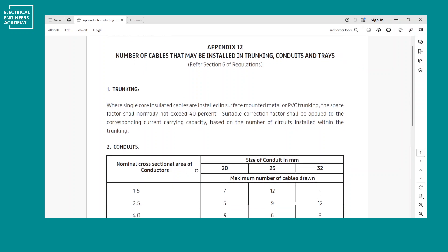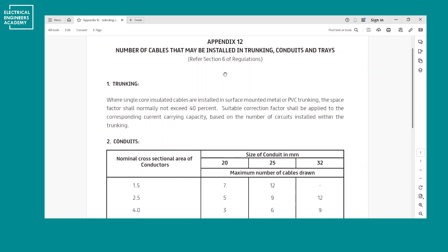Now let's cover trunking sizing. Where single-core insulated cables are installed in surface-mounted metal or PVC trunking, the space factor shall normally not exceed 40%. This is based on the British Standards, and in general the IEC standards. This 40% is the well-accepted filling capacity for trunking.